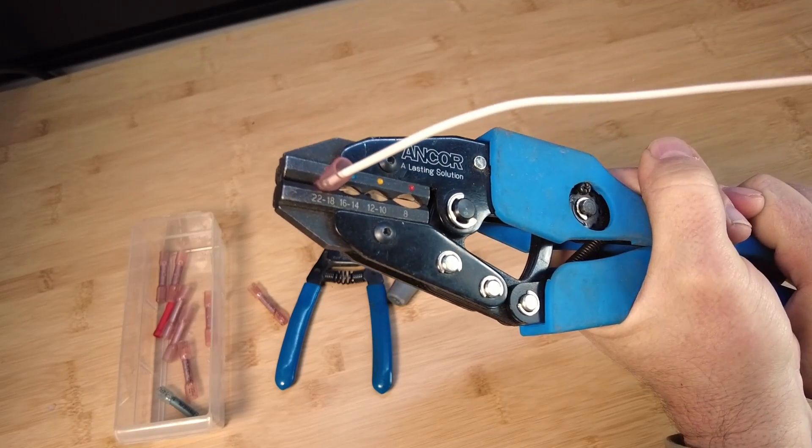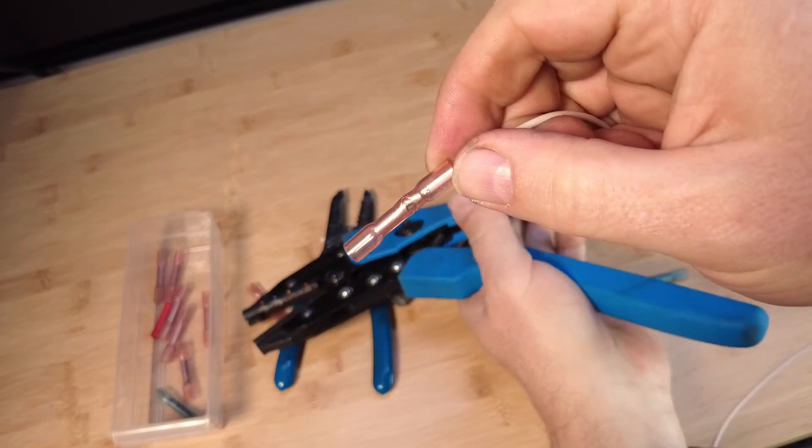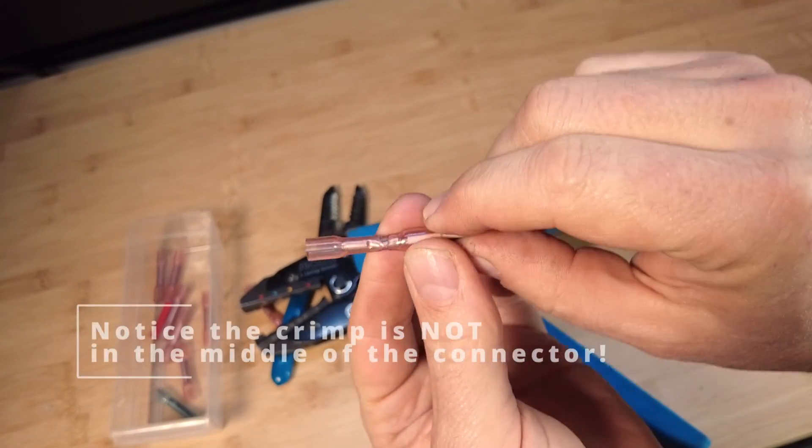Again, it won't let me over or under crimp it and then release. So there you go. There's your crimp. We didn't break through the casing, the insulation, and I can't easily pull it out.